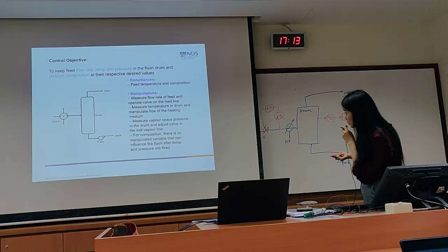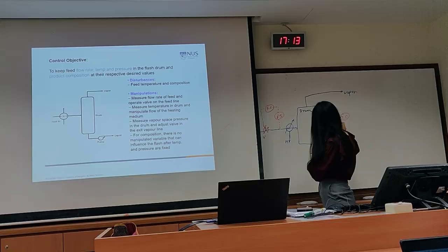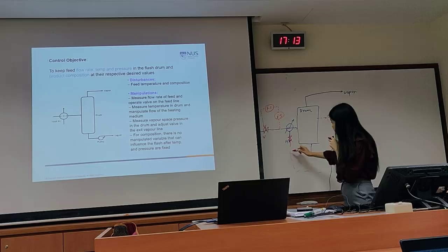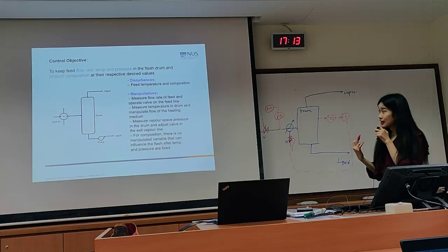Because you have the heating medium here, you can send this temperature signal back to the flow here. By changing this valve position, you'll be able to change the heat exchanger duty to manipulate the temperature in the drum.